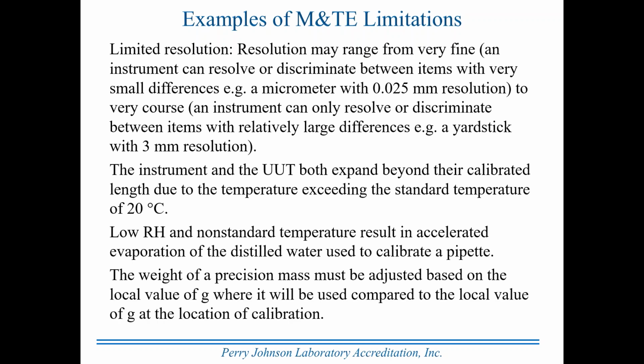The weight of a precision mass must be adjusted based on the local value of G where it will be used compared to the local value of G at the location of calibration. In other words, the acceleration due to gravity is dependent on the location. And it changes from location to location based on elevation above sea level, which is farther displacement from the center of the Earth. Also, in particular areas where the Earth material below your feet is more dense than in other places, that can affect it also because the denser material would increase the value of G.